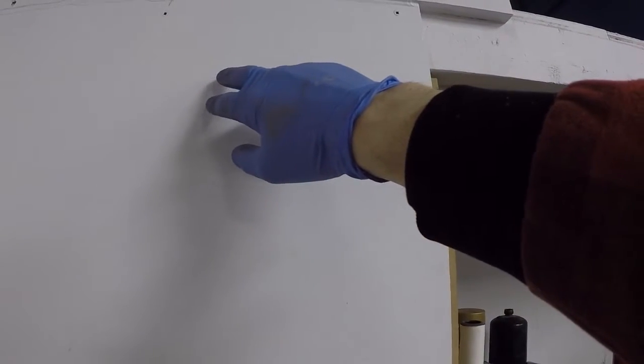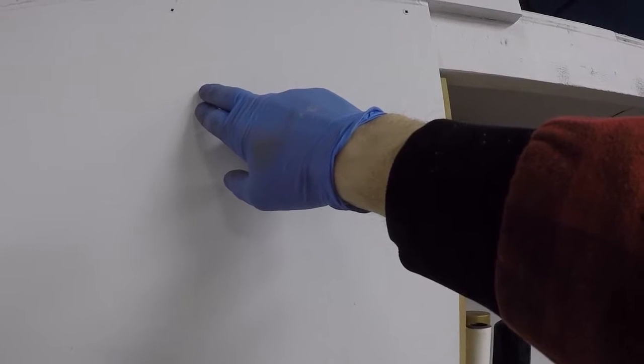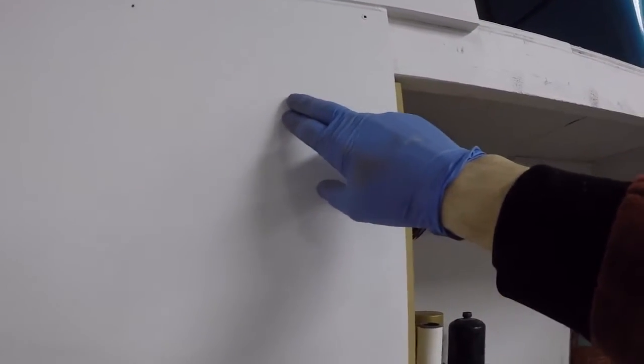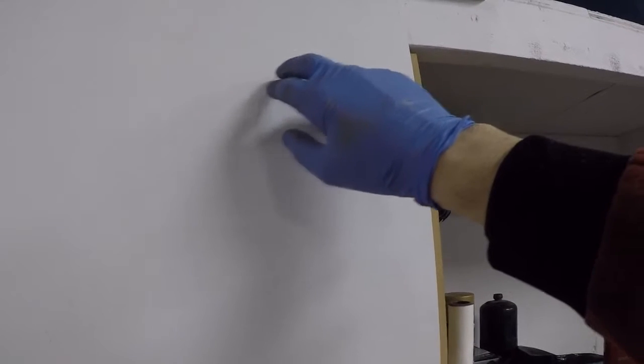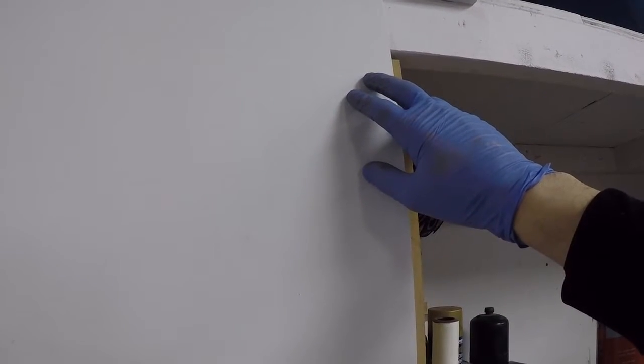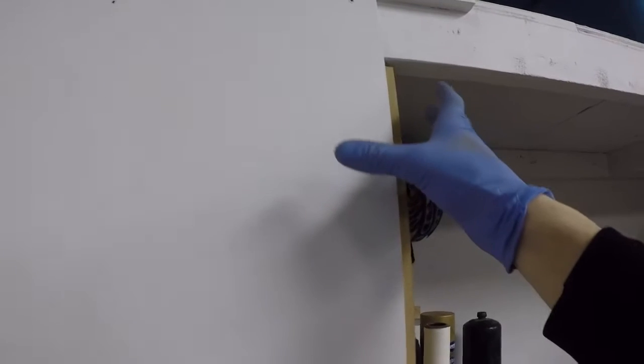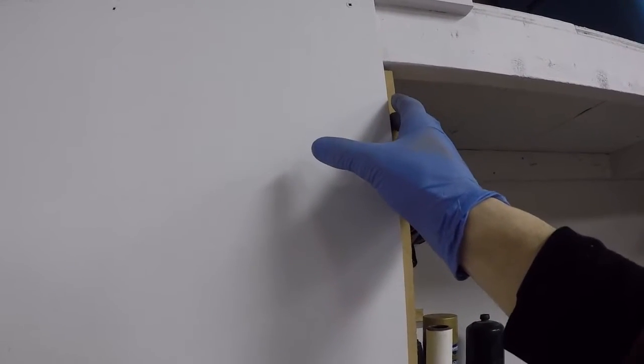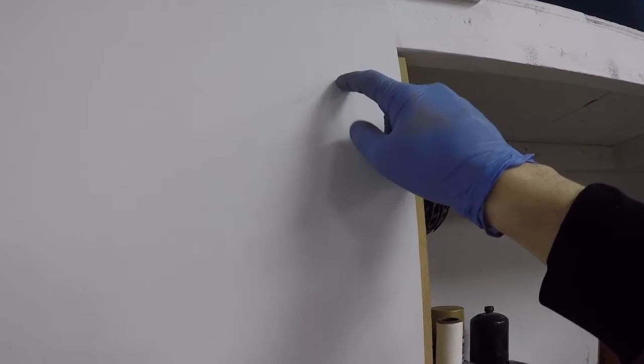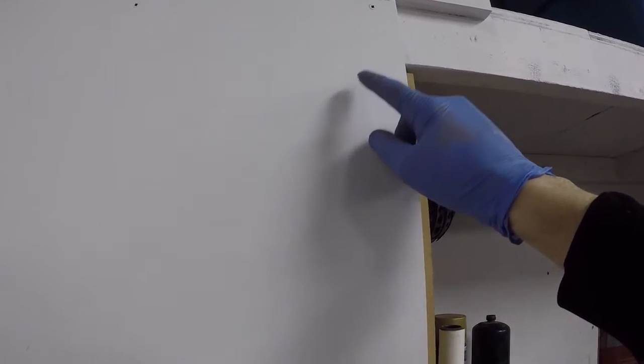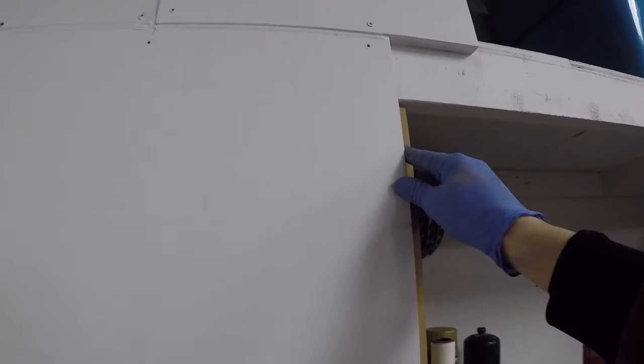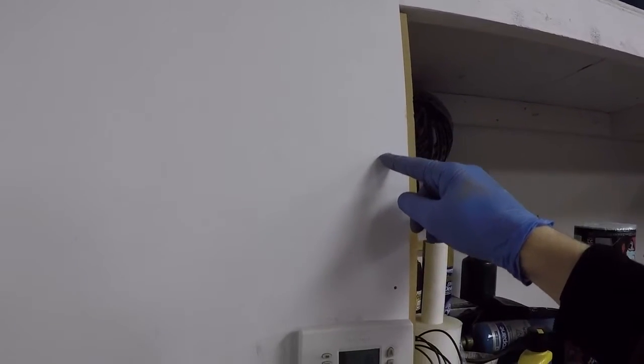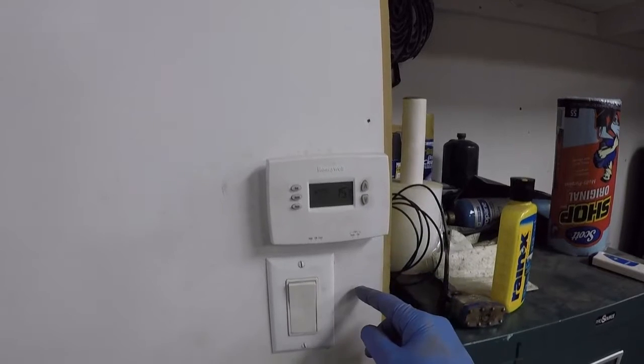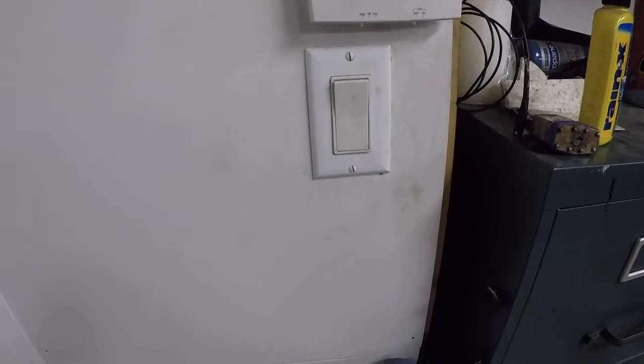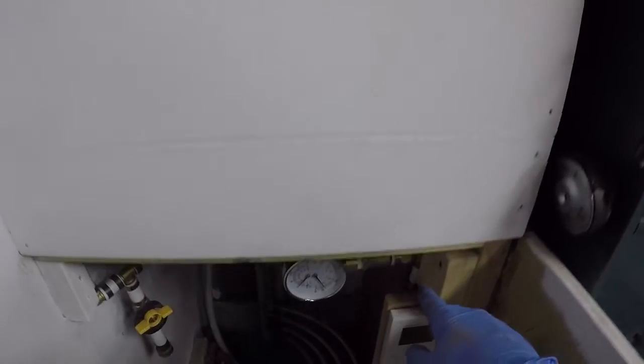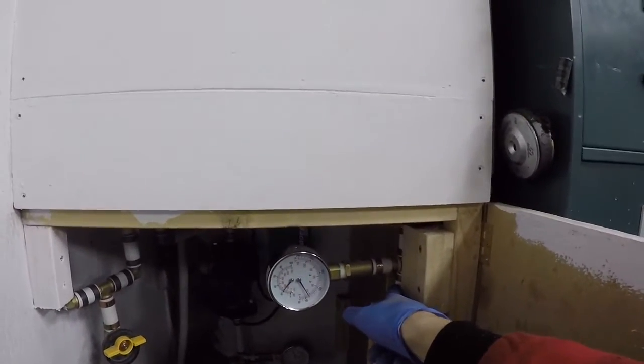So we have the air bubble that got trapped in here, and it's moving quite fast through the 3/4 inch tubing, but as soon as it gets into here, all of a sudden it slows down. It goes into a very large area and it slows down. Now, in order for that air bubble to get back into the system, it would have to defy the laws of physics and fight its way down through 3 feet of water before it could get down to here and make its way out.